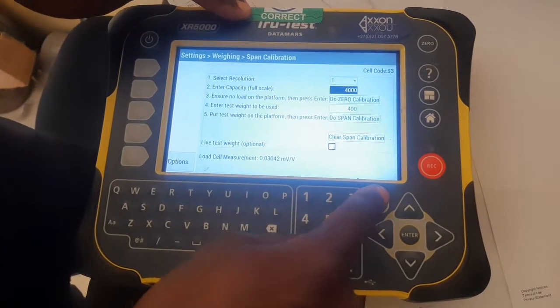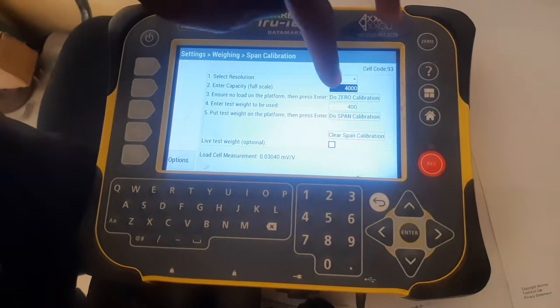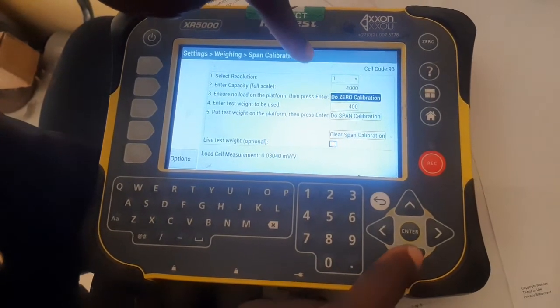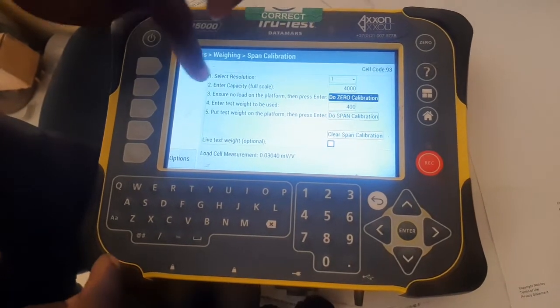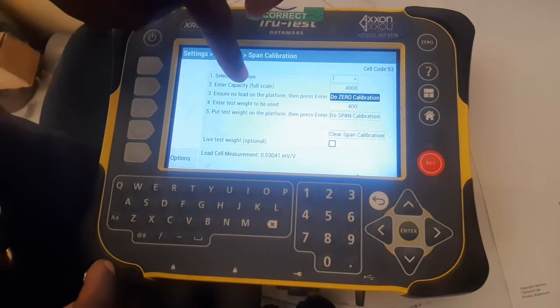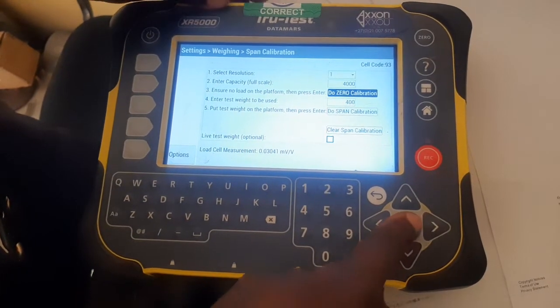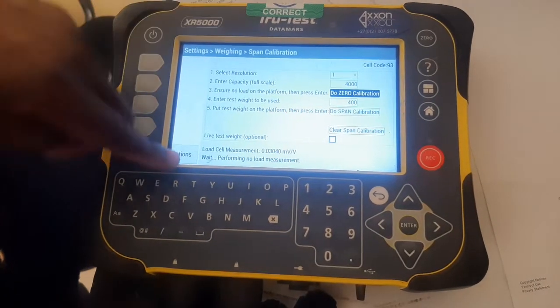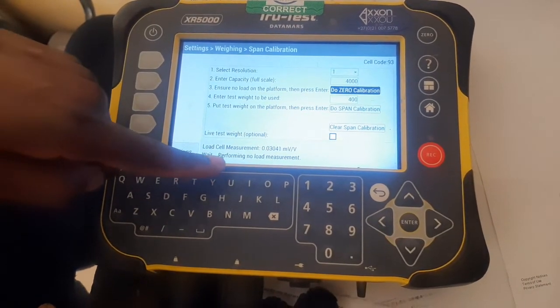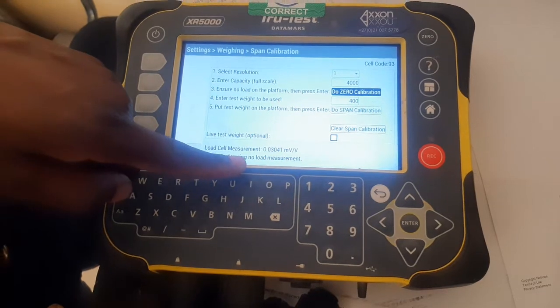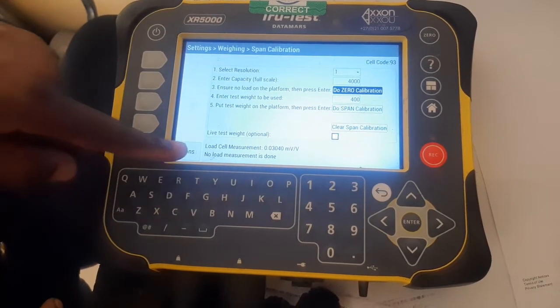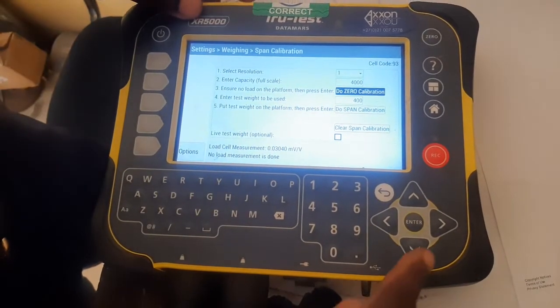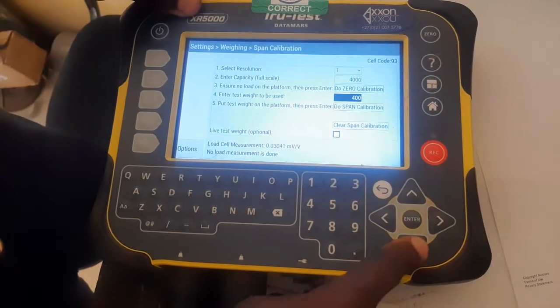To do zero calibration, go down and ensure no load is on the platform. Press enter. It will show you it's performing no load measurement. When that's done, continue.